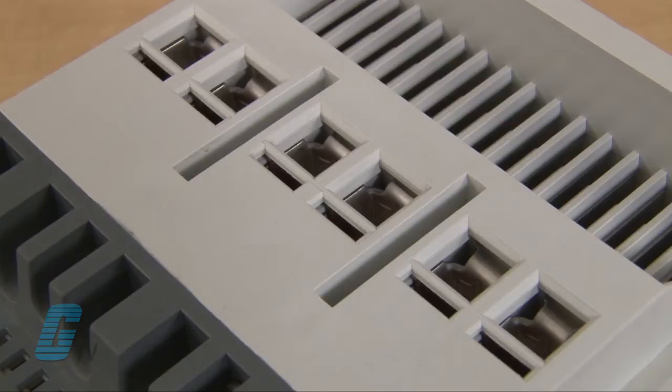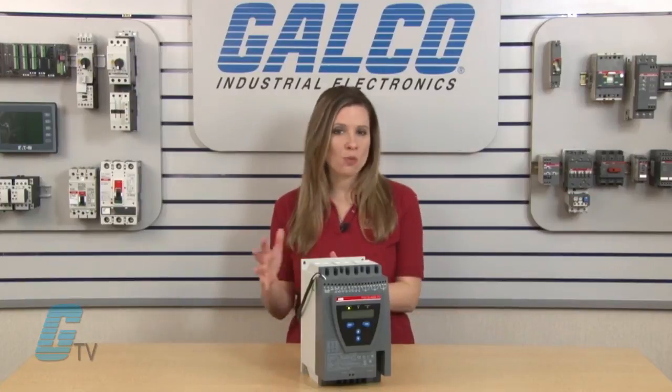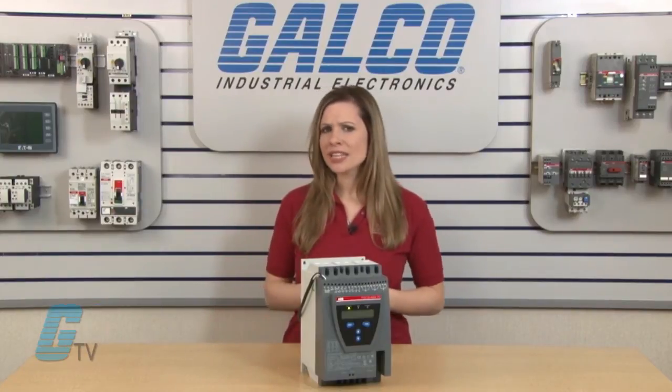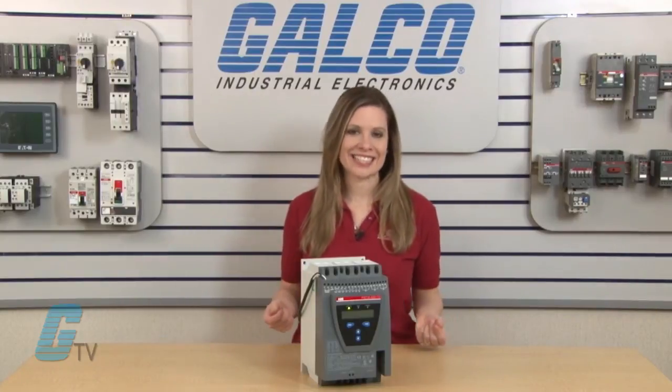The PST soft starters are equipped with extra terminals making the connection of an external bypass contactor easier and allowing all protections to be active during bypass. On the PSTB soft starters, an ABB AF contactor is already built in, ensuring a compact starting solution with minimal wiring during installation.